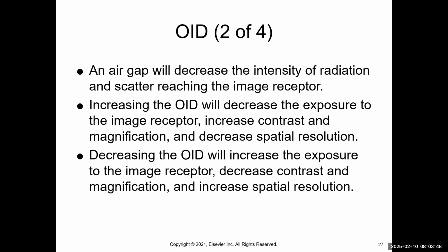Decreasing the OID also... wait a minute. I'm reading this last one as saying increasing. Decreasing the OID does decrease magnification and it does improve spatial resolution. Sorry.